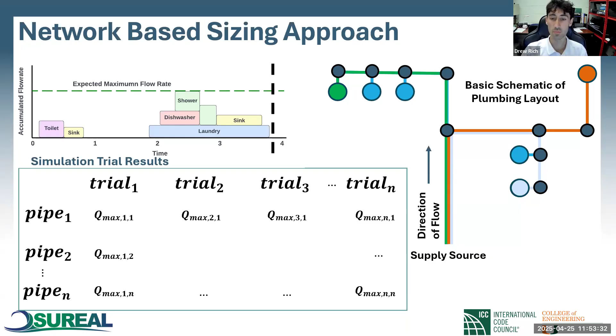And then we can take these flow rates and create distributions. So over all of the trials, we create an expected outcome of maximum flow rates that this pipe may experience. Now, I'm going to jump back one second and say that as we get further away from our end nodes, our terminal nodes, or we get more and more fixtures that are a part of a pipe, the probability that we have higher loading is going to decrease, because we have a lower probability that we're going to have multiple fixtures on at once. So the pipes that are leading up to an individual fixture are most likely going to be very specifically related to that fixture, whereas upstream of these, where we have multiple fixtures, it's going to be a lot less than the total maximum capacity.